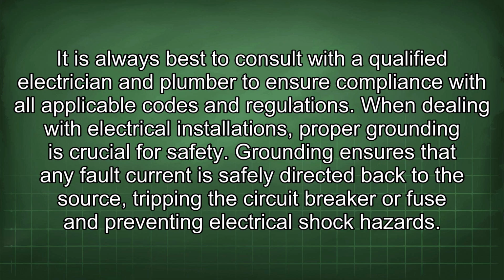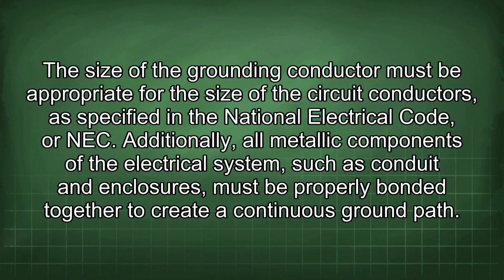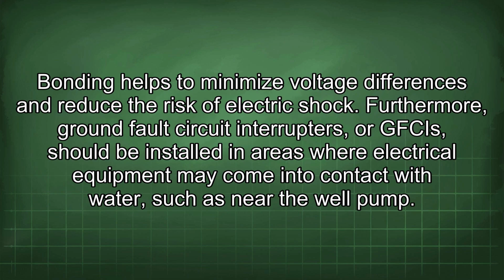Grounding ensures that any fault current is safely directed back to the source, tripping the circuit breaker or fuse and preventing electrical shock hazards. The size of the grounding conductor must be appropriate for the size of the circuit conductors, as specified in the National Electrical Code, or NEC. Additionally, all metallic components of the electrical system, such as conduit and enclosures, must be properly bonded together to create a continuous ground path. Bonding helps to minimize voltage differences and reduce the risk of electric shock.